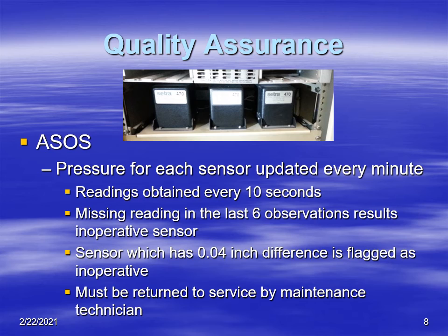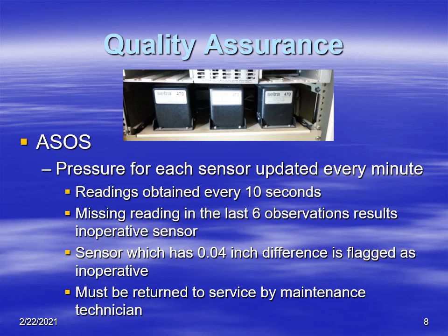If there's a missing observation from one of the pressure transducers, then that pressure transducer is flagged as being inoperative. If there is a difference of more than four one-hundredths of an inch of pressure between any of the sensors, then the one sensor that is most off is also flagged inoperative, and it can only be returned to service by a maintenance technician. So this provides a little bit of background on quality assurance and also exposure error as it relates to pressure measurements.